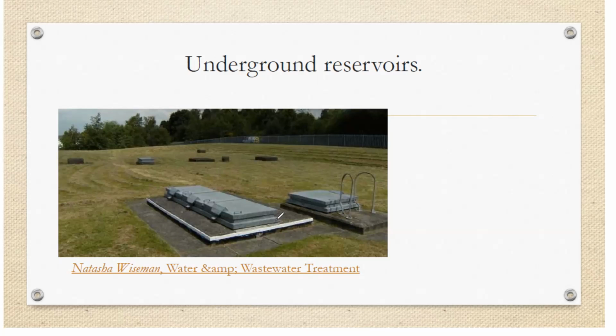Okay, so even if there is an ESR, the GSR has to be built, because ESR has two tasks: to store the water as well as to make water available to the public by gravity. If there is no ESR and you want to supply water to the public from the GSR, you will have to pump directly, and for each individual consumer the water will be provided through pumping, and that is not economic, not possible. That's why with ESR, we pump the water up to a short distance.